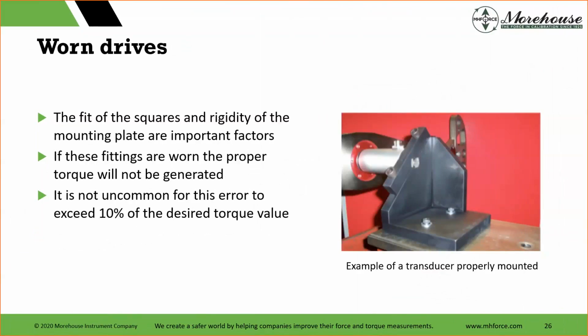This is why I'll show you, we designed something with a hexagonal drive. Still will wear. Hexagonal's great. It'll still wear, but it won't wear as fast because you have 6 surfaces instead of 4. But if the fittings are worn, the proper torque will not be generated. They'll be loose, they'll be slack. It's not uncommon for this error to exceed 10%. Another big, huge error. So a 10% error, when you calibrate the cell and go for a wrench, is going to be huge. You're not going to get the wrench in.